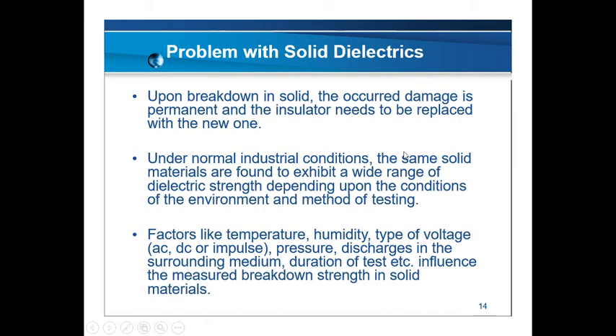Under normal industrial conditions, the same solid material is found to exhibit a wide range of dielectric strength, dependent upon the condition of the environment and the method of testing. The dielectric strength of the same insulator at room temperature would differ from that of the same insulator being used at a very high temperature, because there will be some chemical reactions and stresses going on. So with the same insulating material, based on the temperature, the dielectric strength may differ.